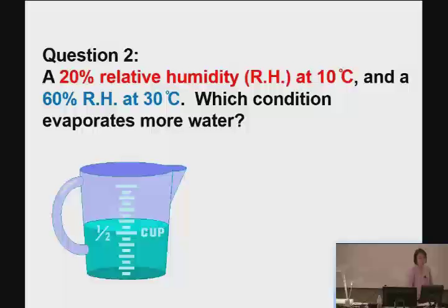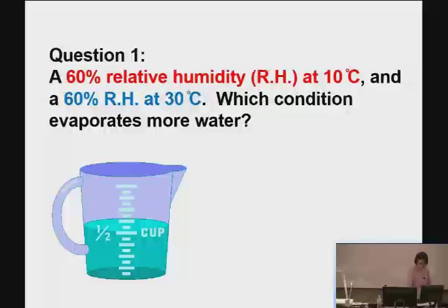So what do you use in this case? Temperature is changing and humidity is also different. Because relative humidity is based on the saturation at that temperature, the base value is changing when temperature changes. So in that case, you need a different value to compare the capacity of the air to hold moisture. That's the driving force of the evaporation. So what is the value? That is VPD.